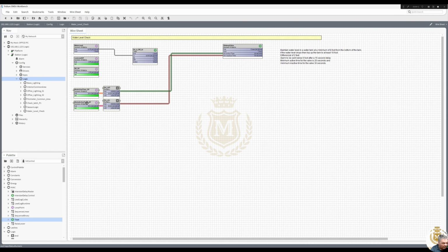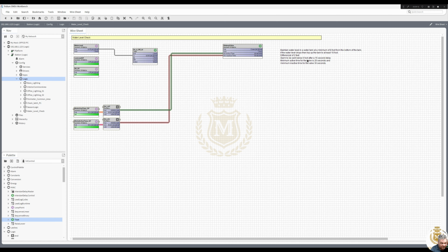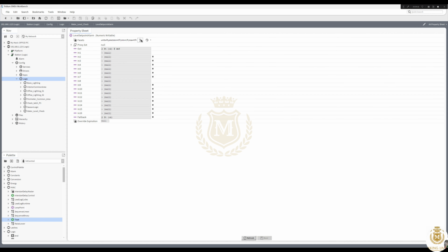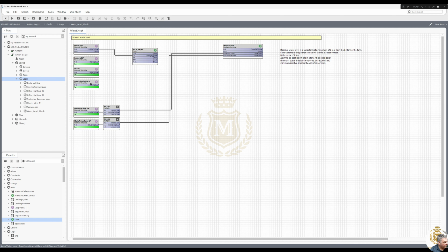And then we've got a set point alarm as well. Alarm to be set below 6 foot. Duplicate. Level set point. Alarm. And we've got 6 foot there. I'll change that maximum to, I don't know, 10 foot. Minimum 1 foot. Save. Action set to 6 foot. So they can only select between 1 and 10 foot there.